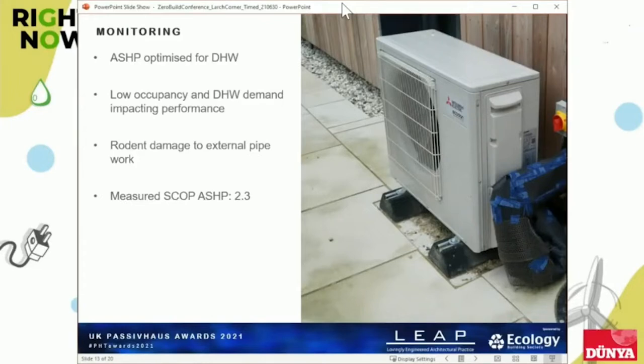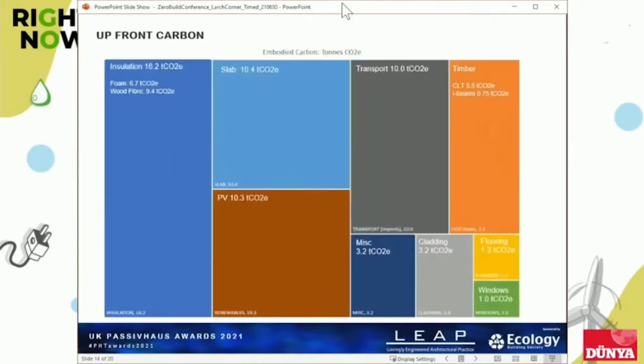In practice, what we found was that it didn't quite perform the way that we expected, because there's lower occupancy than expected, and also there's less domestic hot water use. So that's had an impact on the seasonal performance. And also there was a bit of rodent damage to the external pipe work, which had to be repaired. So that no doubt contributed a little bit to that performance gap.